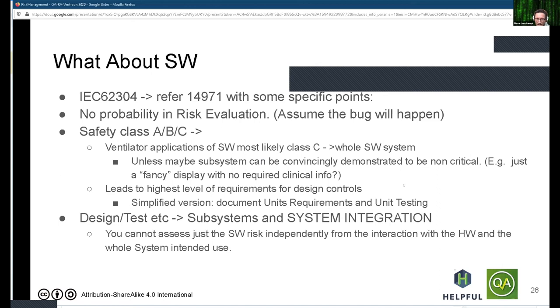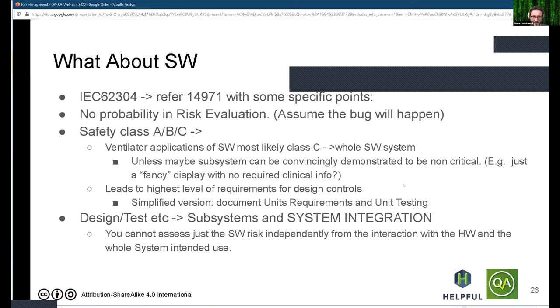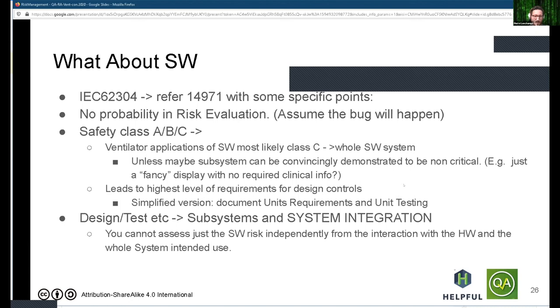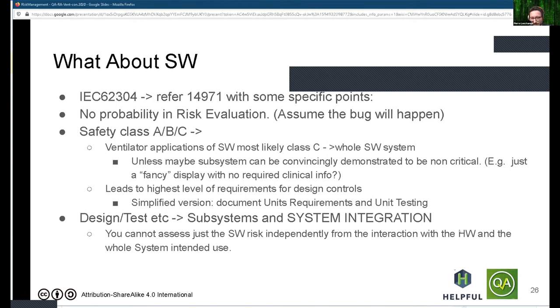A quick word about software. The standard for software is IEC 62304, which refers to 14971 with a couple of specific points — you rate severity only, not probability. There's a specific scale called a safety class. Honestly, I think all ventilator-related software will be classified as Class C, which is the highest, meaning you will have to implement documented requirements and testing for your individual units. Software cannot be designed independently from the hardware system it will be part of, and you need to consider that at all times when writing risk management and implementing risk controls.